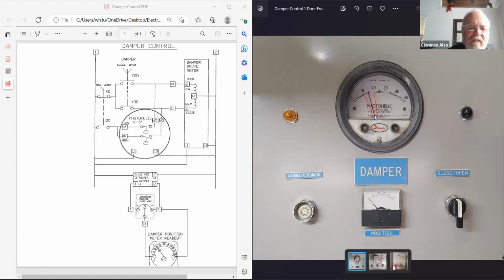So basically what's happening, this here works just fine. But when you put it in automatic, if this open winding is going all the way open and just stays open, and the open light is on all the time, that means we're getting 110 volts there, from this guy right here, and then it comes across there. This is that first red needle, the one that says, okay, I'm not getting enough, let's open up. This right here, that's what that needle is.